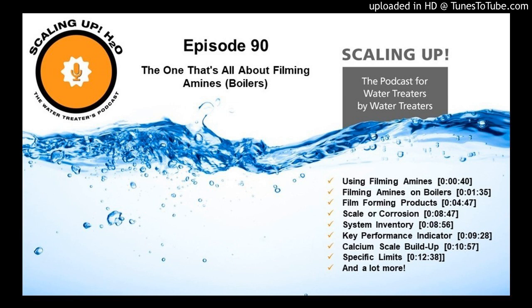And then basically based on a series of calculations and then either best case scenarios or assumptions, right? Whether it runs 100% all the time, or if it runs 70% of its capacity, or if it runs 60% of its capacity, we can do a series of calculations that enable us to make a best guess, and then we can dose based on that. And then ultimately, something that we didn't talk about last week, but I think we can touch on here if it works, is the question of how do we know if we've properly dosed a system, right?